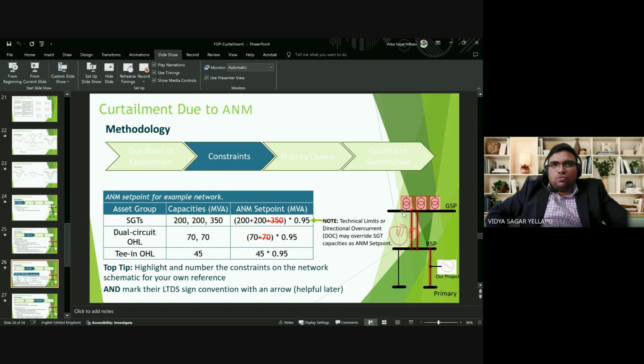There are two dual circuit overhead lines, each of rating 70/70. So, in order to consider the worst case scenario, only a 70 MVA rating is to be followed by this ANM, and it is associated with a derating factor of 95%, or 0.95.